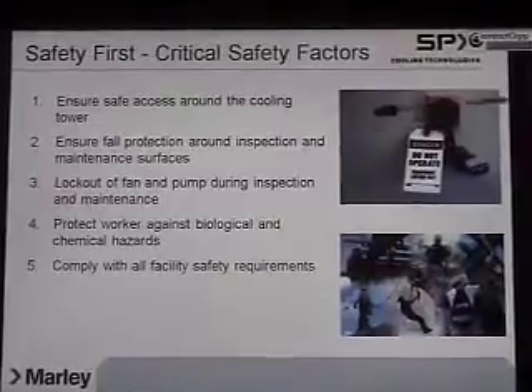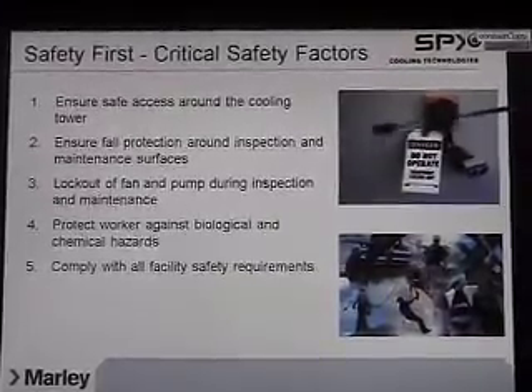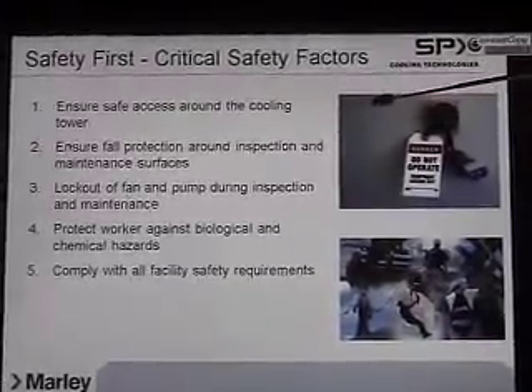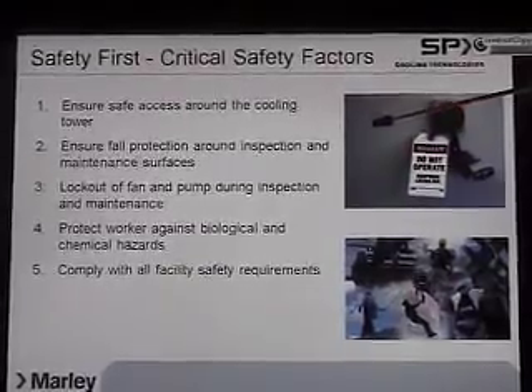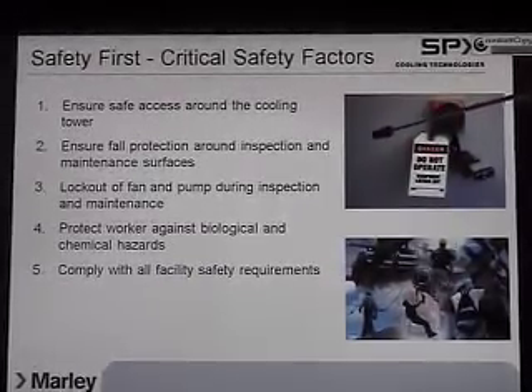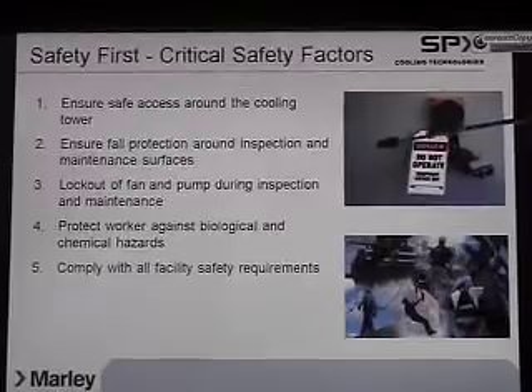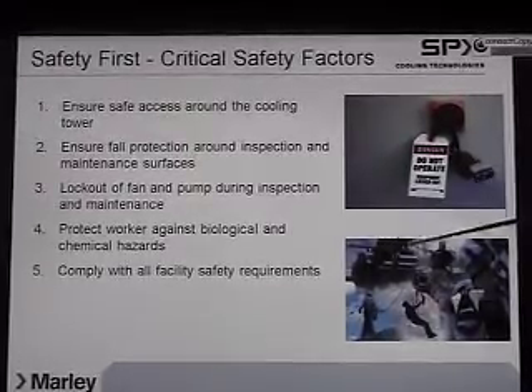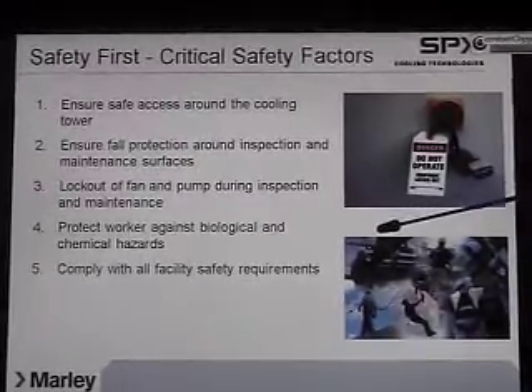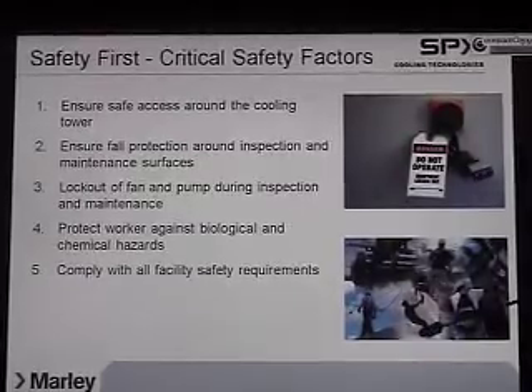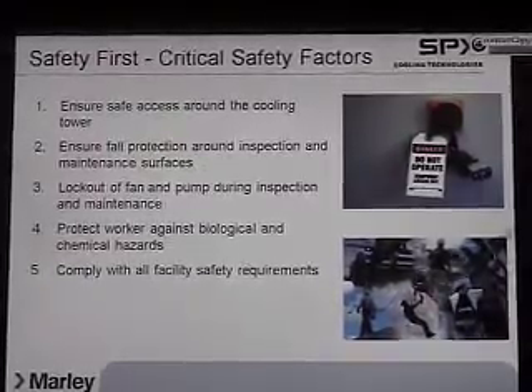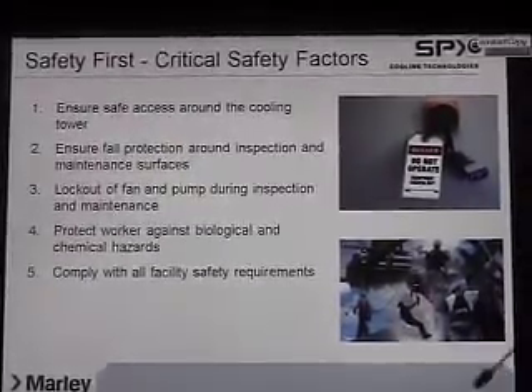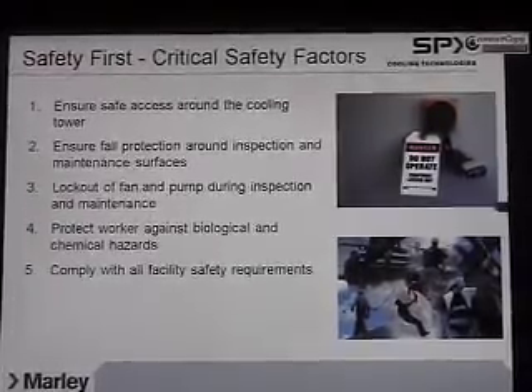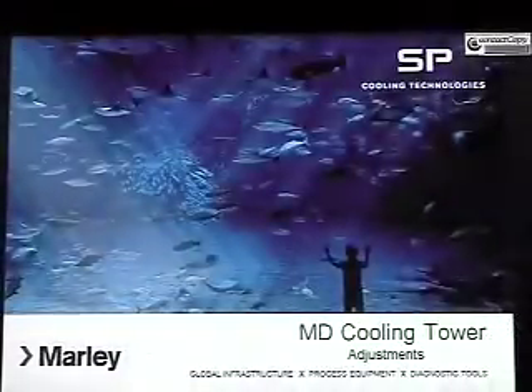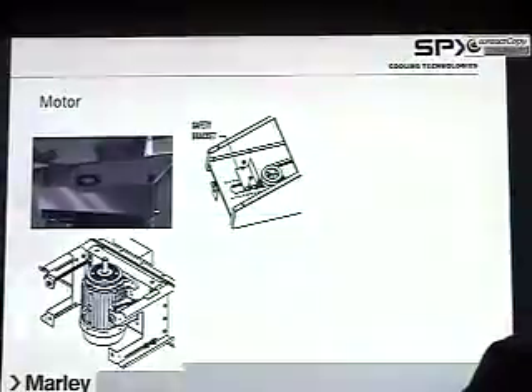Again, please lock out, tag out. You want to make sure that the access around the tower is safe. There's no ice pond out there. And again, Legionella is a concern with cooling towers, and proper water treatment and keeping your water clean will help prevent that. Since it is a killer, we can't stress that enough.